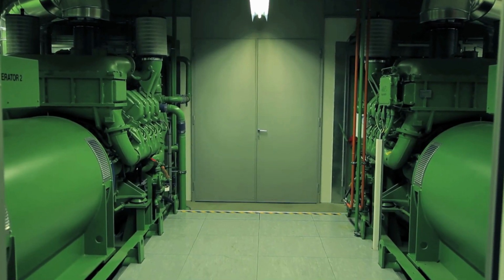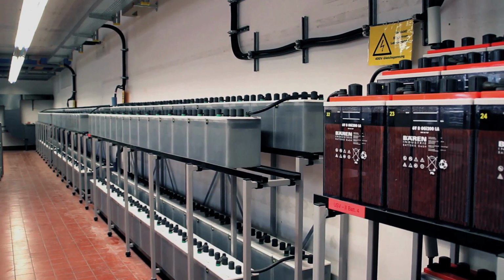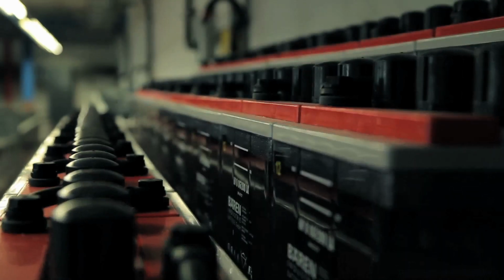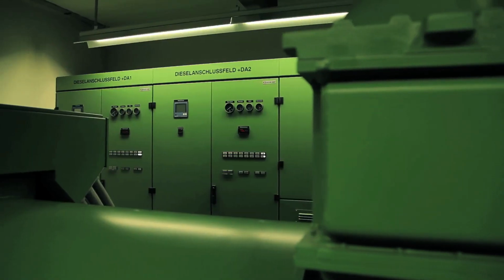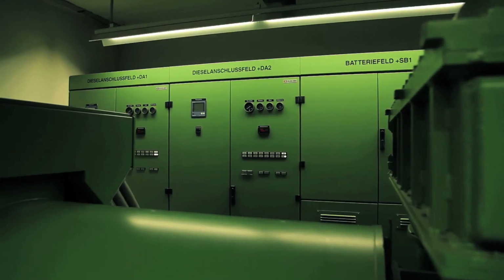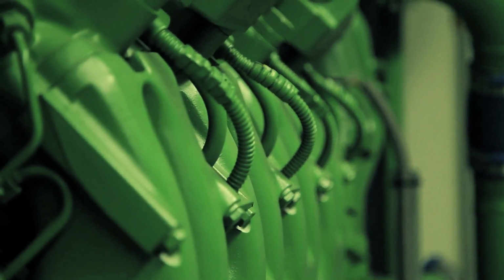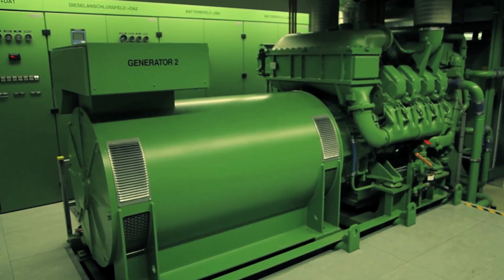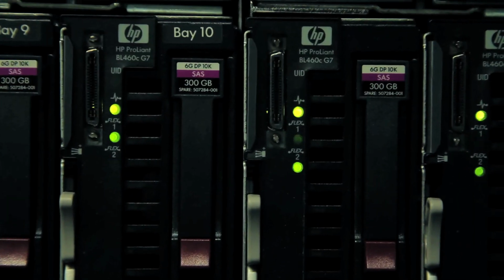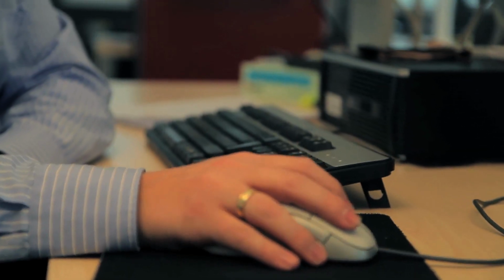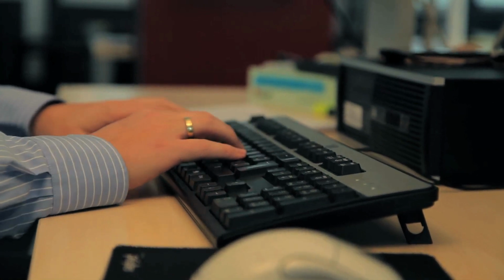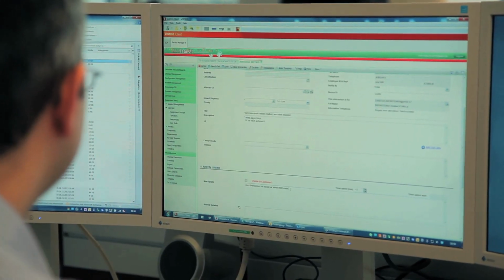Huge diesel tanks combined with 2 generators, each supplying about 700 kilowatts, further back up the redundant energy connection of the whole facility, making it nearly impossible to shut down the power supply for the facility. Storage, virtual servers and even applications can be moved between the locations in an instant, done automatically in case of errors.